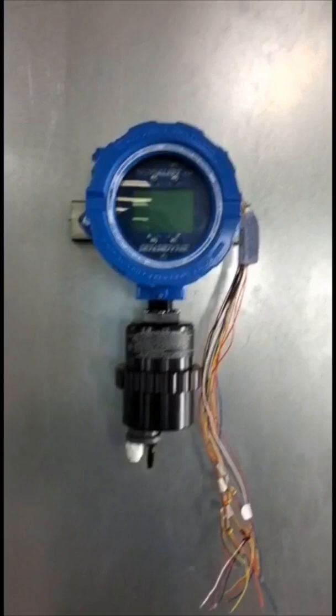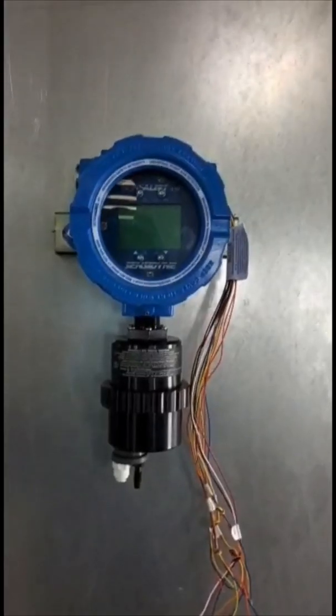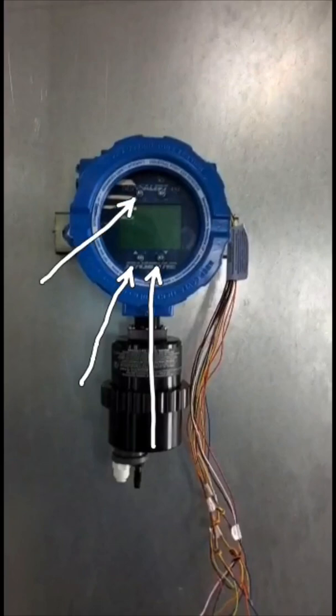The second thing I want to point out are these right here, right here, right here, and right here. These four look like screws, but they're actually magnetic sensors. For us to go into the settings and change the calibration, change the vapor type, or see any alerts, we actually use a magnet to touch each of those as needed to toggle through our settings. That's another part of the explosion-proof design of this—there's no touchpad underneath there, it's all done by magnet, which is actually pretty cool.